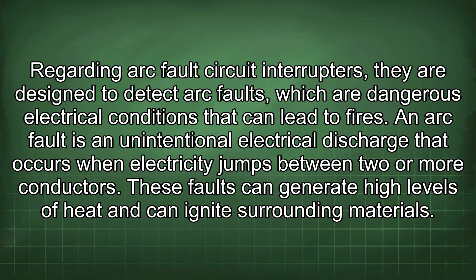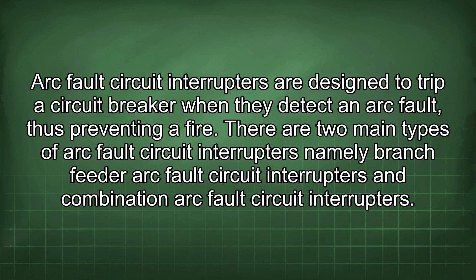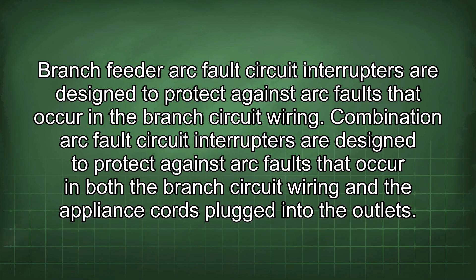Arc fault circuit interrupters are designed to trip a circuit breaker when they detect an arc fault, preventing a fire. There are two main types: branch feeder AFCIs, designed to protect against arc faults in the branch circuit wiring, and combination AFCIs, which protect against arc faults in both the branch circuit wiring and the appliance cords plugged into outlets.